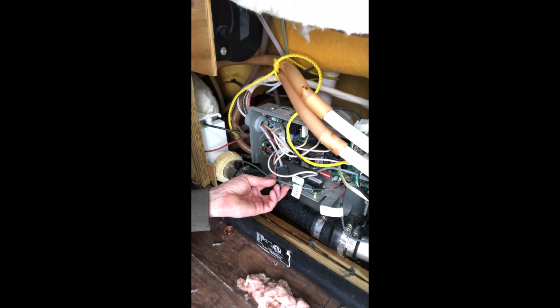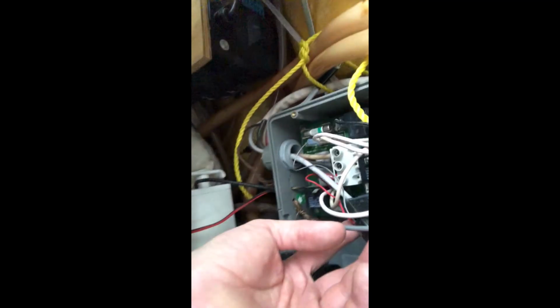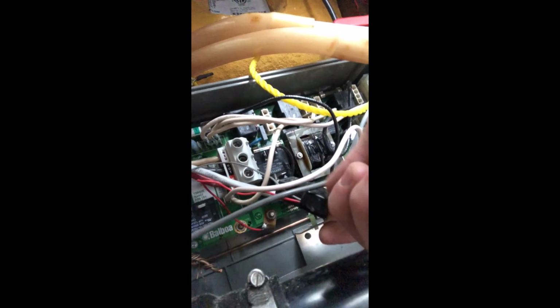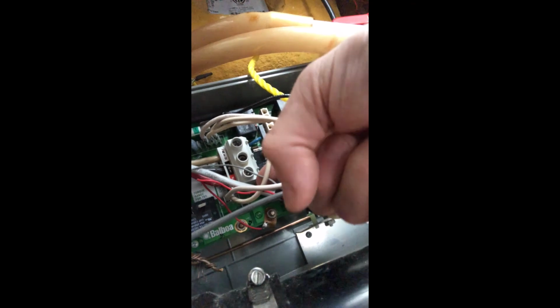But what we got here is a little 120 volt relay trying to run off of one leg of the 220 volt. I'm not going to touch it, but you can see it in there. 220 volt power lugs that used to run the electric heating element. So when there's a call for heat, theoretically this relay will kick in and the signal goes out on this wire to the garage, and that turns the boiler on.